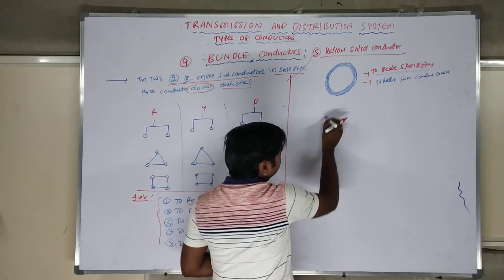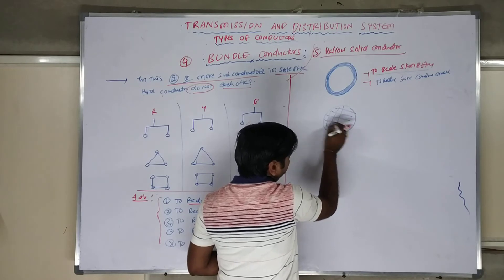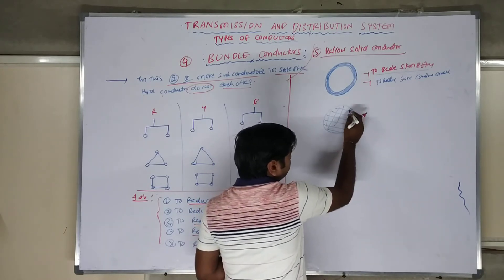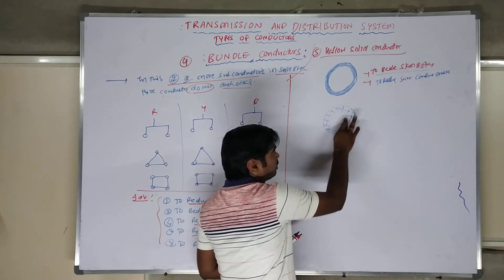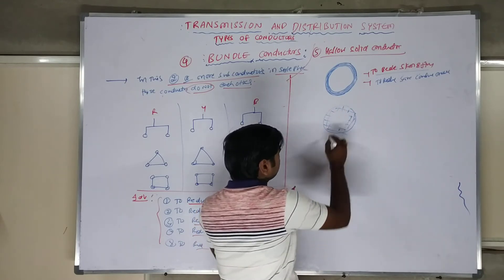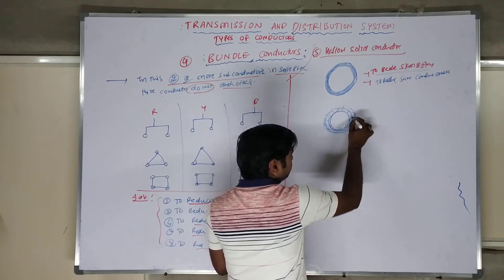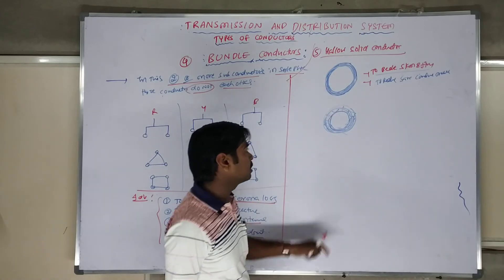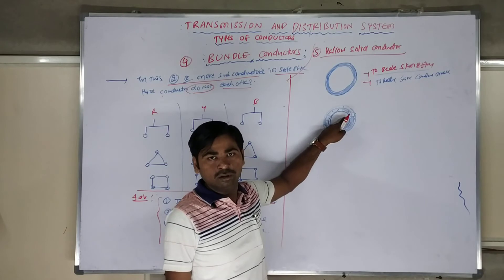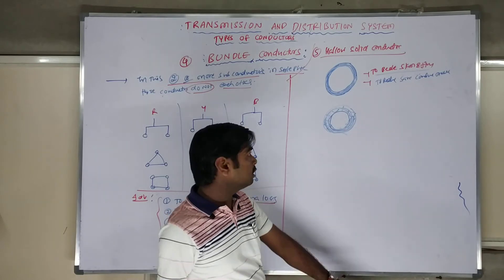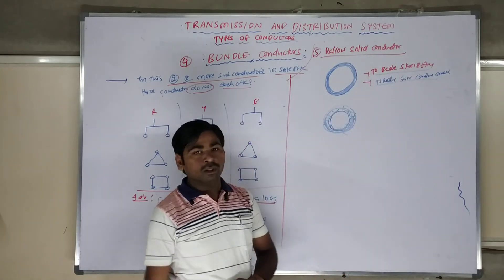Let us understand this. If we take a total complete solid conductor material, the current flows only on the outer surface area due to the skin effect. So the inner portion is not useful. That is what causes the skin effect — wasting of the conductor. If we remove the inner material, we can save the conductor material. This is the concept of a hollow solid conductor.